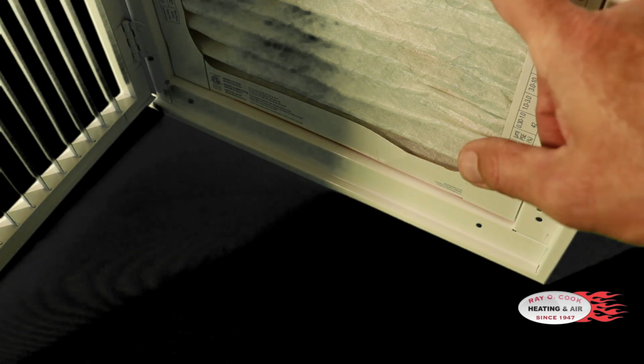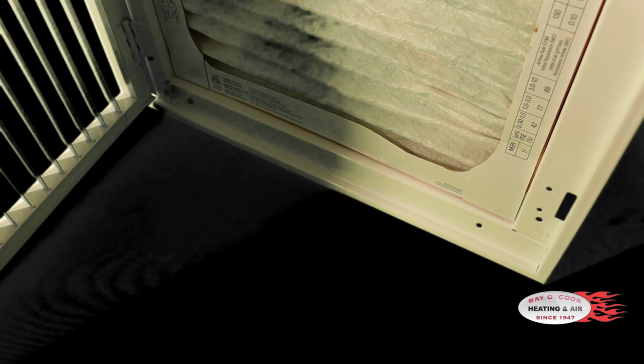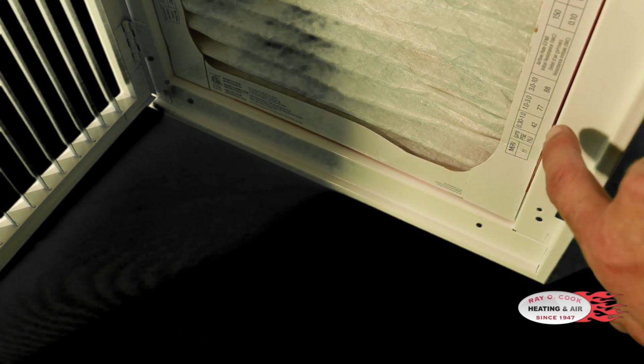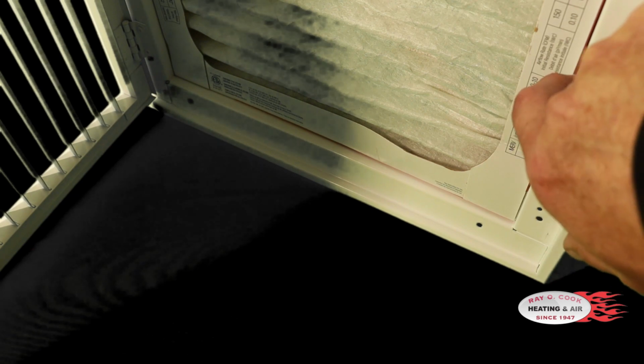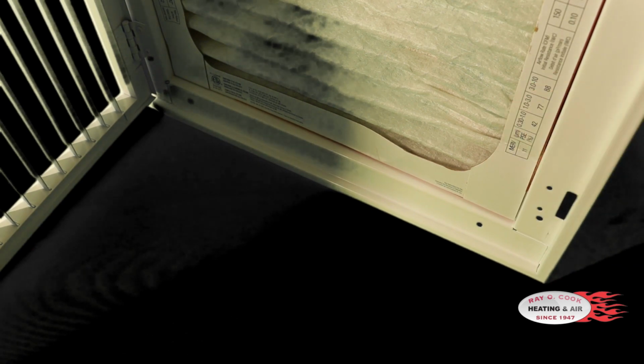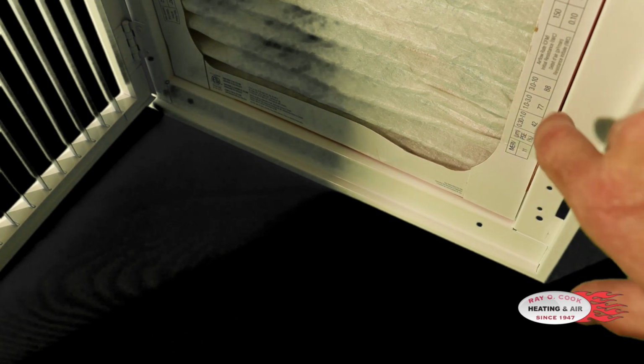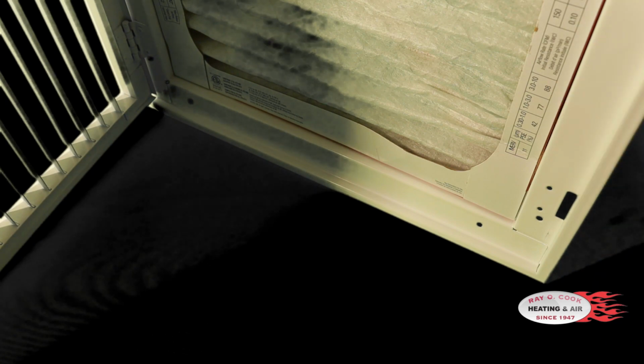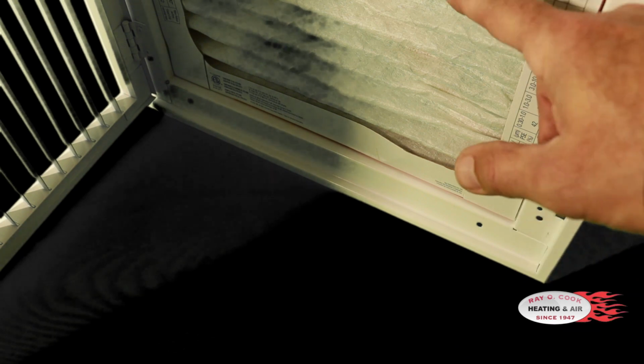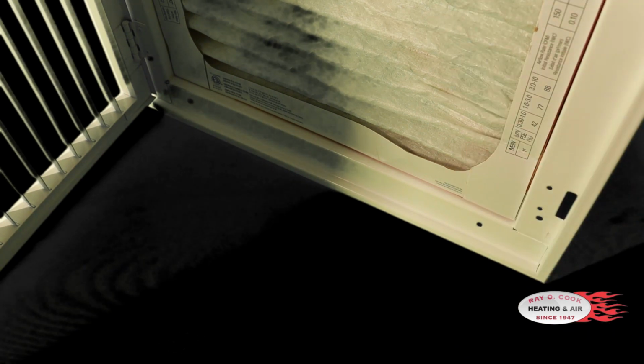So if you increase the restriction with a more efficient MERV rating, you literally can suck more particles past your filter, which is called bypass. So we're bypassing the filter. So we got this really good filter to catch the particles at a real high rate here, but a lot of the particles are going right by the filter because the pressure is too great on the filter, the resistance, and we're just sucking air around the filter.